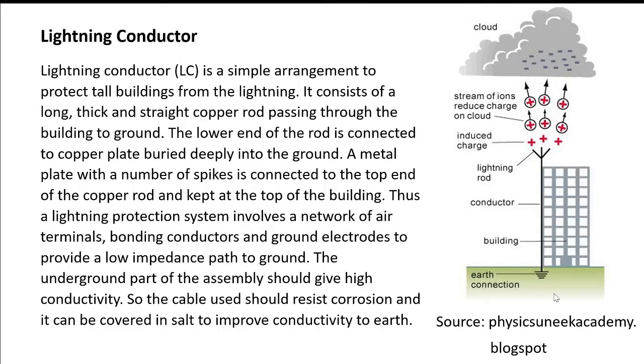Now let us discuss lightning conductor. What is a lightning conductor? A lightning conductor is a simple arrangement to protect tall buildings from lightning. Here, the diagram shows the arrangement of a lightning conductor to protect buildings from lightning. It consists of a long, thick and straight copper rod passing through the building to the ground. The lower end of the rod is connected to a copper plate buried deeply into the ground. A metal plate with a number of spikes is connected to the top end of the copper rod and kept at the top of the building.